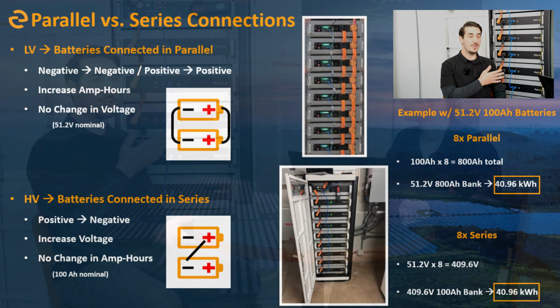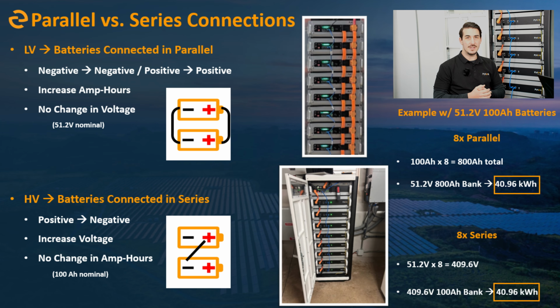It's important to note, though, that sometimes we can make high voltage sound better than low voltage, as if it has some secret hidden energy we're unlocking, but that's really not the case. If you look at a system with 8 high voltage batteries and a system with 8 low voltage V5 batteries, the amount of energy in both systems is the same—8 batteries times 5 kilowatt hours is still 40 kilowatt hours total for your bank. All that's changing is either the voltage or the amp hours, using a different connection method.